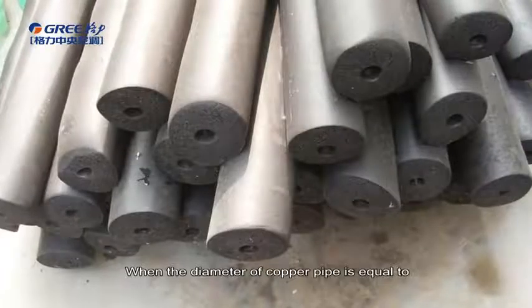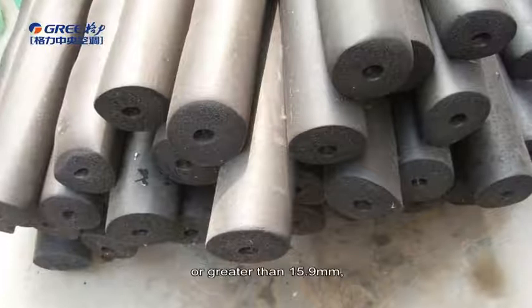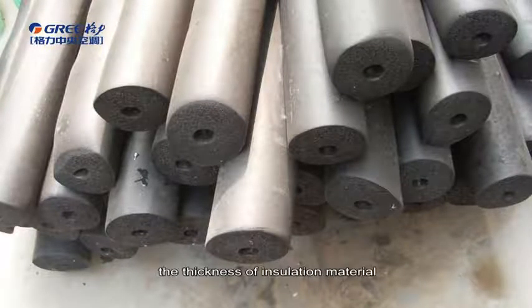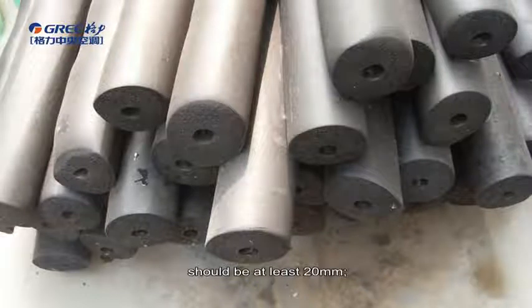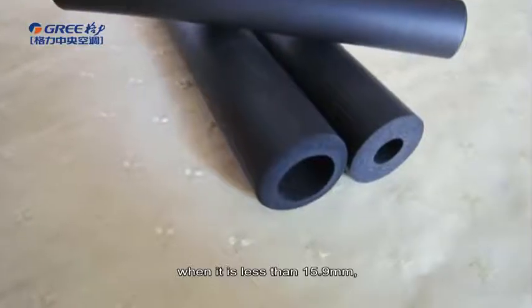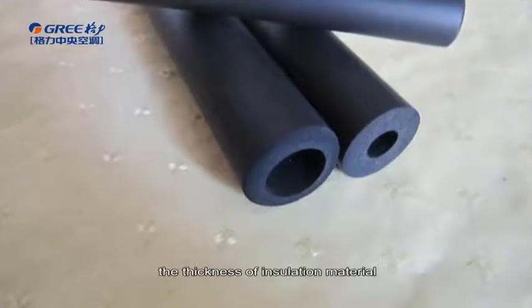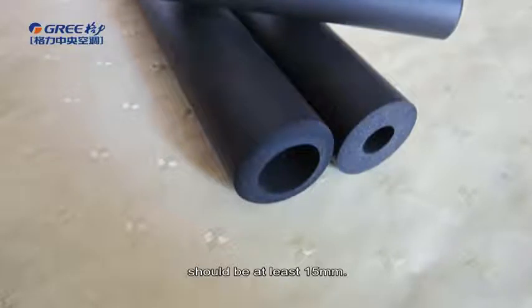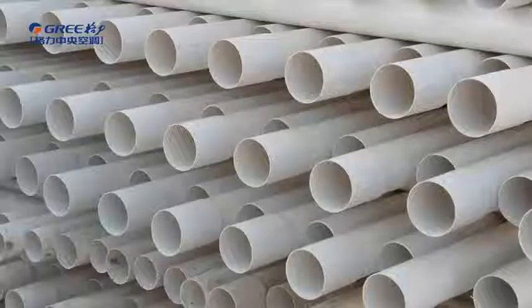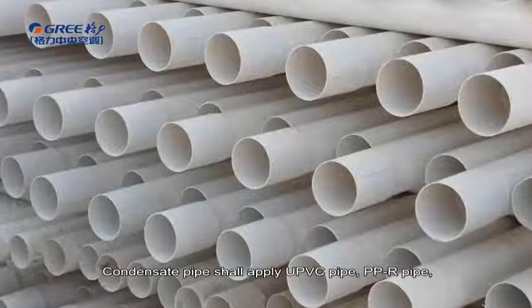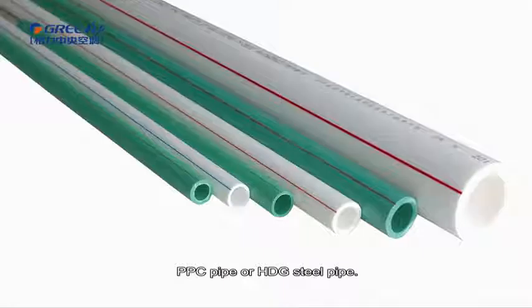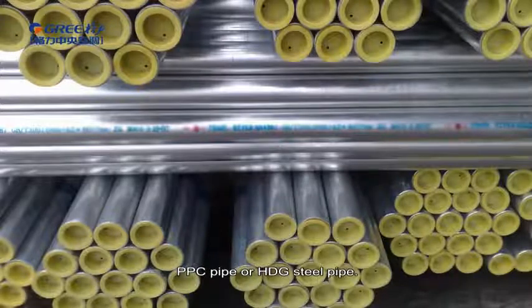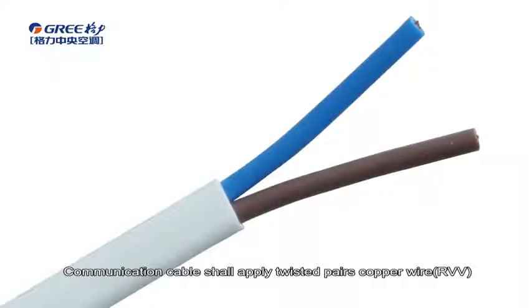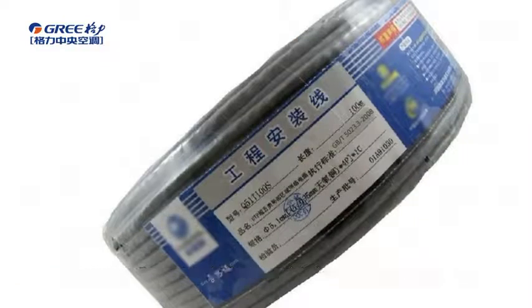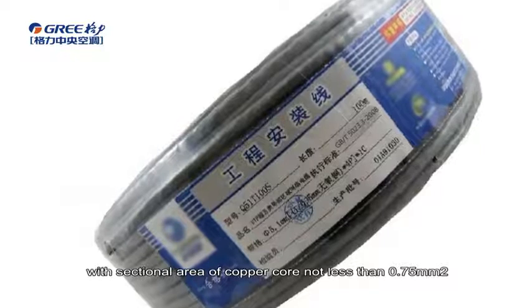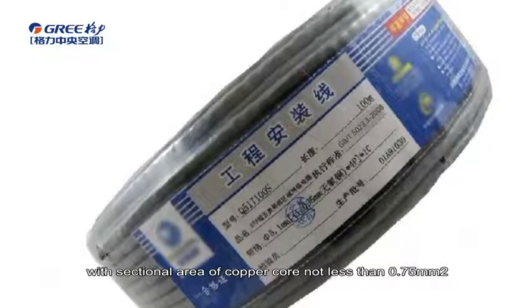When the diameter of copper pipe is equal to or greater than 15.9 millimeters, the thickness of insulation material should be at least 20 millimeters. When it is less than 15.9 millimeters, the thickness of insulation material should be at least 15 millimeters. Condensate pipe shall apply UPVC pipe, PPR pipe, PPC pipe, or HDG steel pipe. Communication cable shall apply twisted pairs copper wire with sectional area of copper core no less than 0.75 square millimeters.